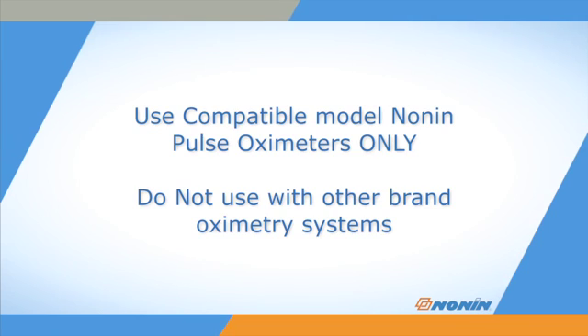Nonin Flex sensors are designed for use with a wide range of Nonin oximeters. Remember, Nonin sensors are designed for use with Nonin-brand pulse oximeters only. Do not use Nonin-brand sensors with other brand pulse oximeter devices, which may provide inaccurate results.